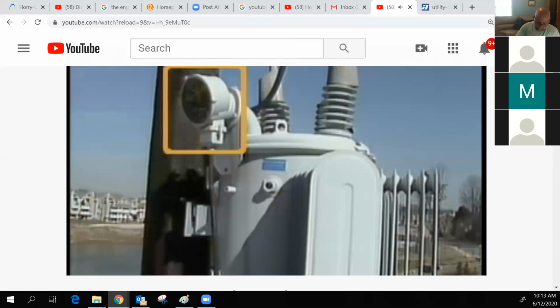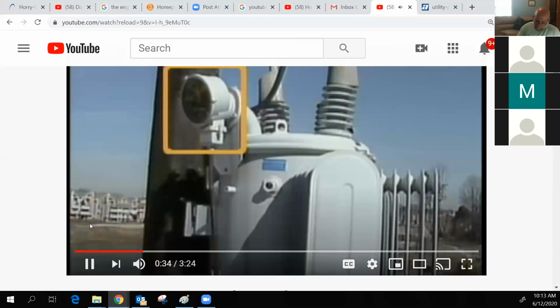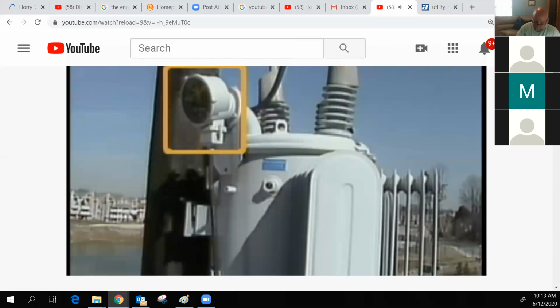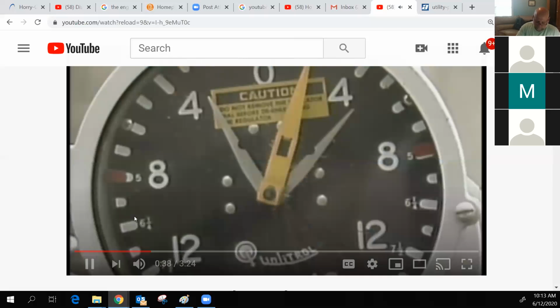Surge arresters are connected to the line and load bushings. This dial, called the position indicator, is mounted on the tank so that it can be viewed from below. The dial has a scale, which has a 0 or neutral position in its center. Additionally, there are 32 marks indicating the 16 steps above and below the 0.